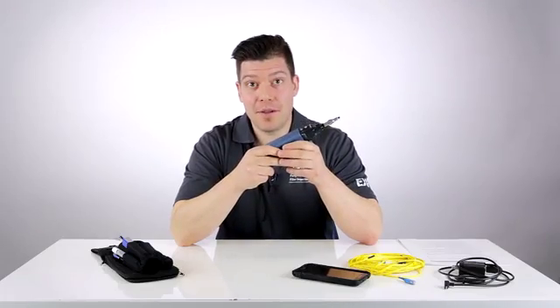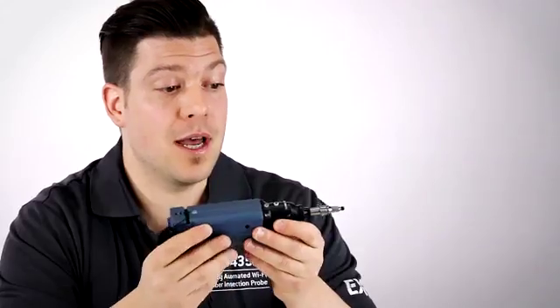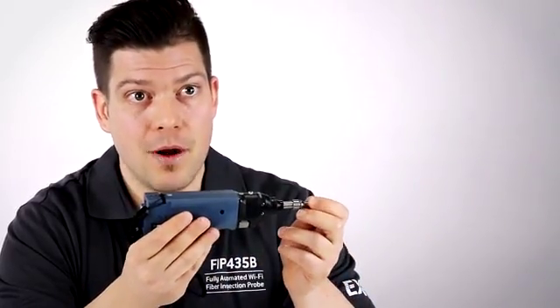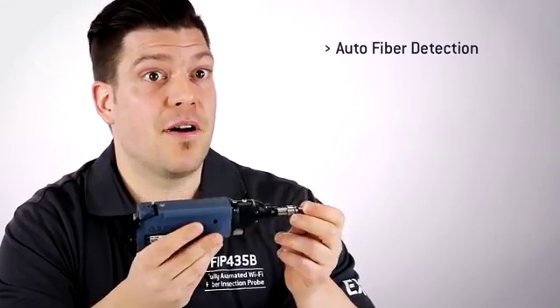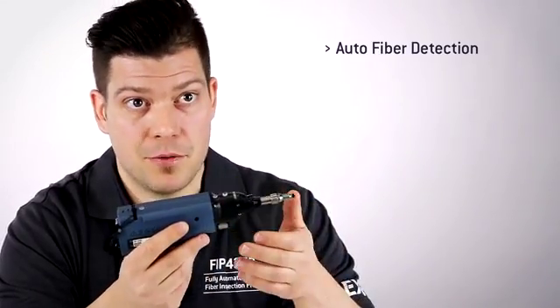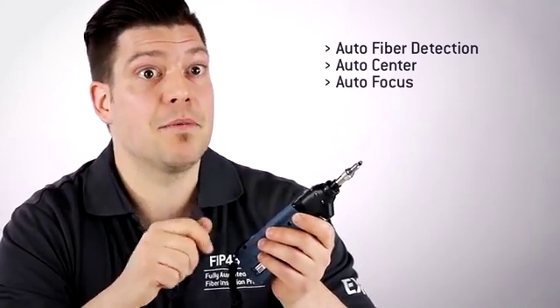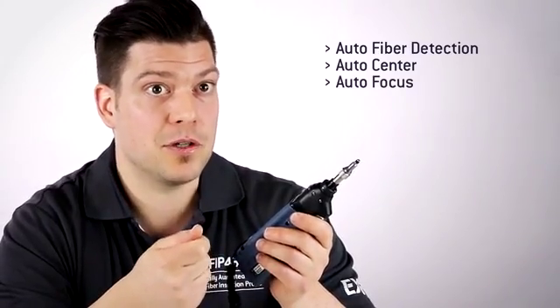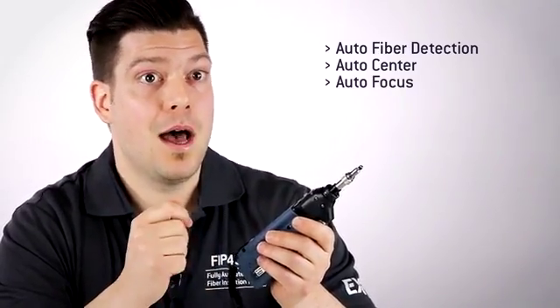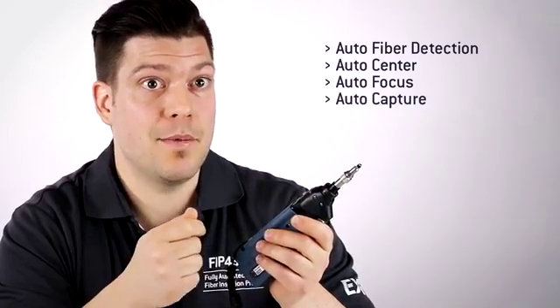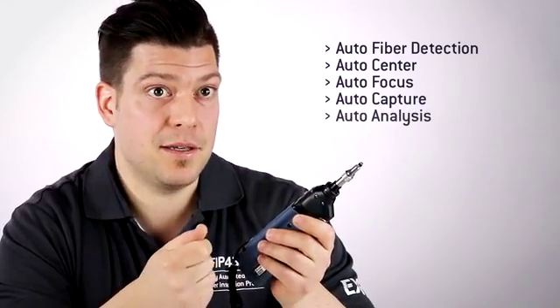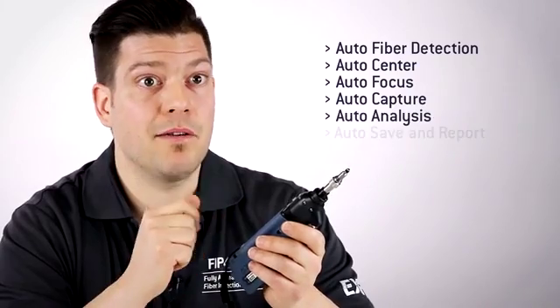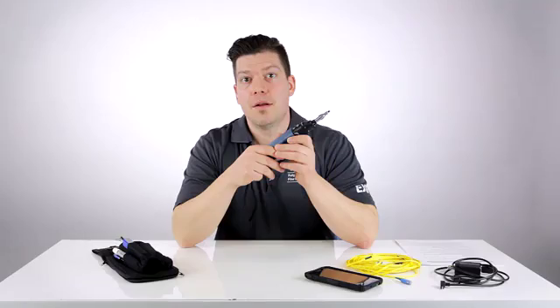What we mean by fully automated test process is that the user simply has to connect the tip of the probe into the connector and the probe will recognize there is a fiber inserted and trigger the process to start. It will find and center the fiber image, adjust and optimize the focus, capture the image, run the analysis, provide you with a pass-fail result, and save and report automatically.